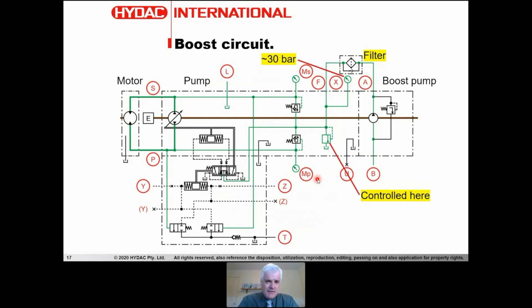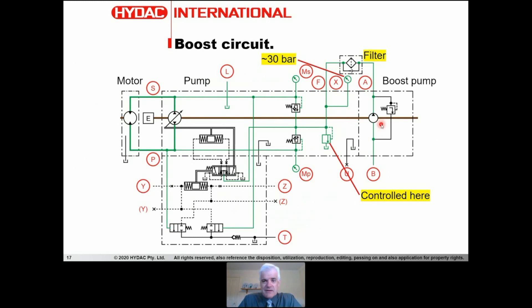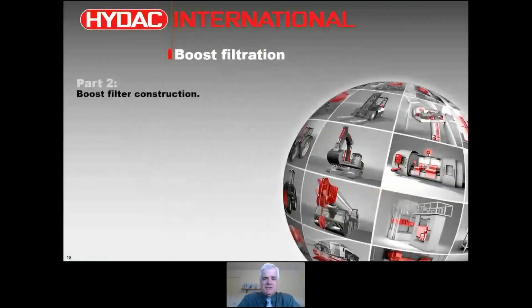This is not a high-pressure application in absolute terms, but pressure rating still matters for filter selection. It is a fixed displacement pump running at constant flow and constant pressure. Filtration is straightforward here and doesn't need to be a very large filter, since the boost pump is typically around 20 percent of the main system flow.